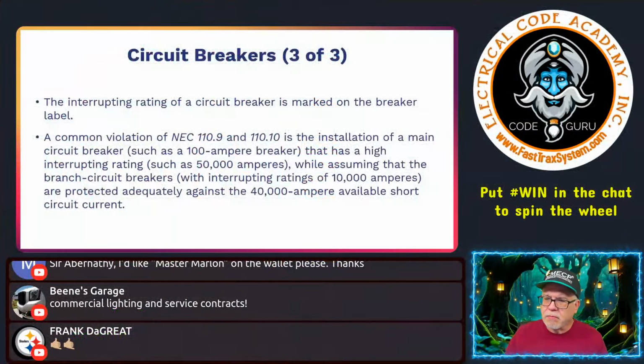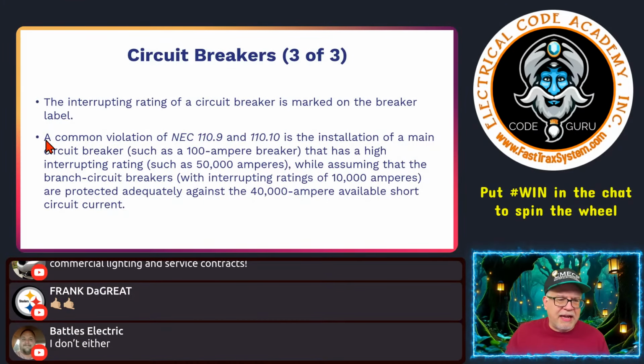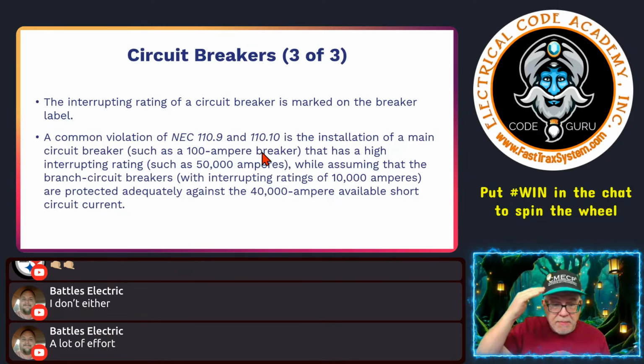Sorry. All right. So a common violation of NEC 110.9 and 110.10 in your NEC is an installation of a main circuit breaker, such as a 100 amp breaker. So mentally think about it. So they're putting in a main breaker, and it's 100 amp. That has a high interruptive rating, such as 50,000 amperes, okay? While assuming that the branch circuit breaker with an interruptive rating of 10,000 amperes are protected adequately against a 40,000 amp available fault current, okay?